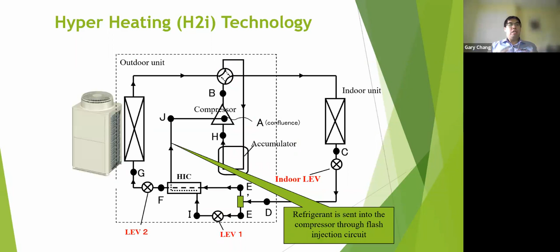So how does it work? Imagine it's in heating mode, shooting out hot refrigerant. That hot refrigerant becomes cold refrigerant through the indoor unit because it's releasing all the heat. Some part of that cold refrigerant, before it goes back to the condenser, actually goes into the compressor to cool it down so it can run at a higher frequency to generate more heating capacity, doing more work to the refrigerant.